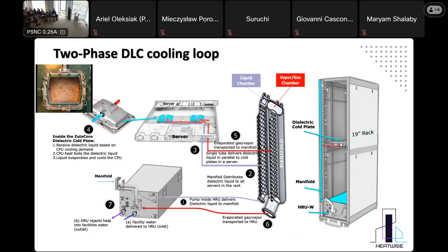You have the manifold on the side. The liquid comes up through the manifold into the server, and into the cold plate inside the server. When it boils and turns into vapor, the vapor goes out through the red line into the manifold, down to the heat rejection unit, and is condensed back to liquid, and so forth. This is how it works.